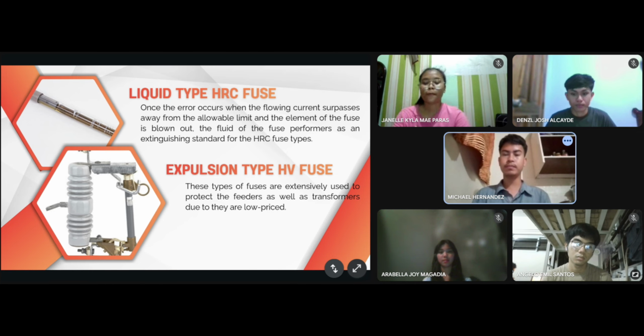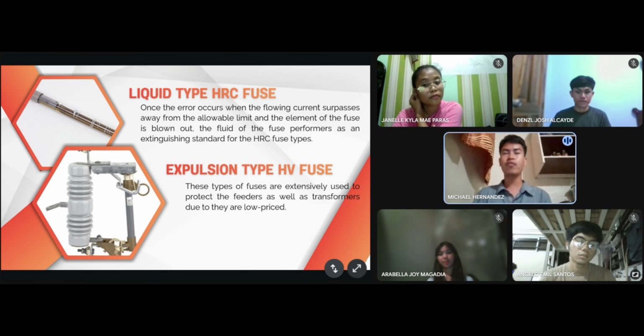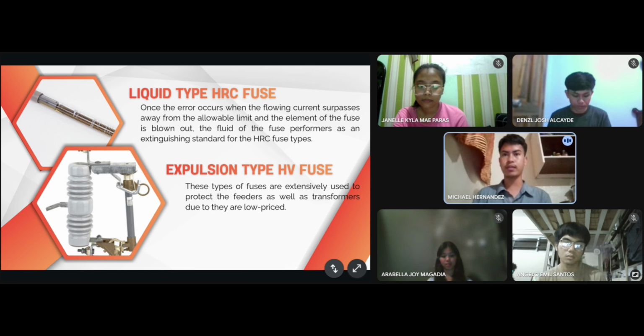So the next, the other type of fuse is the expulsion type HV fuse. It's a protective device used in electrical power systems to safeguard things like transformers and distribution lines from overcurrent or short circuit faults. What makes this type of fuse unique is how it extinguishes or expels the electrical arc that forms when the fuse melts due to excessive current.